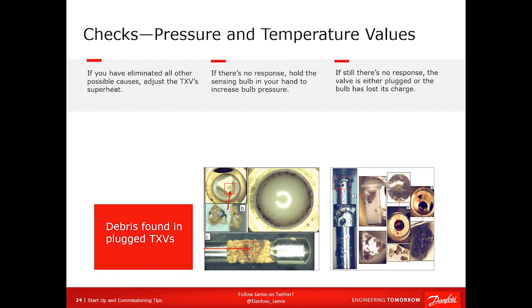If the valve is non-responsive, that's a problem, because yes, we tell you to wait 10 or 15 minutes in between adjustments. However, when you decrease the TXV superheat setting, the valve will open up immediately and put more refrigerant into the evaporator, and you will see an immediate change. It takes time for that to balance out, but you will see an immediate change. So if you do a couple of turns on that spindle and nothing happens, hold the sensing bulb in your hand. If nothing happens, pull that valve out.